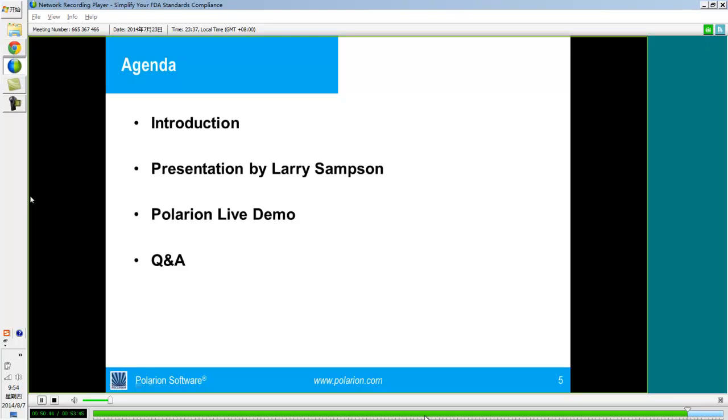Great. The second question, also for you, Larry, essentially is, in the context of a template, what does it mean to be ISO 62304 compliant? Oh, well, that's a good question. So the ISO 62304 is a standard really focused on medical device software, and so you can imagine that it has all kinds of requirements that are really not related to the template. One example of that is how the maintenance of the software is going to be done. And when you have a change to some object or some unit of software clear down in the design, what impact does that have on the progression of the software up through the assembly? And what testing would have to be done to revalidate or re-verify that software, either one.